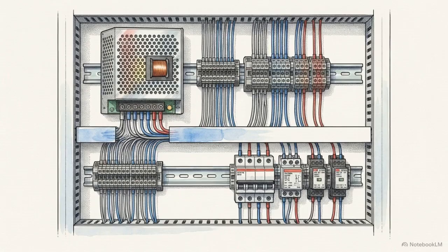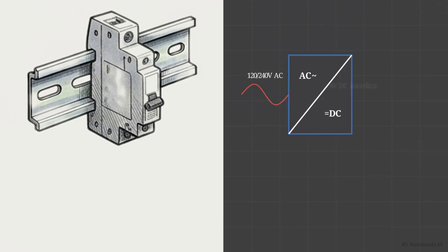The bedrock of any modern control panel is the 24-volt direct current power system. This split diagram shows the starting point, the switched mode power supply, or SMPS. Factories run on highly volatile alternating current. The SMPS rectifies that unstable AC mains power into a flat, predictable 24-volt DC baseline.